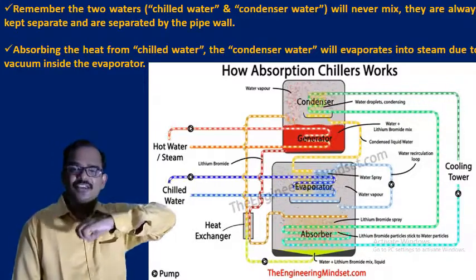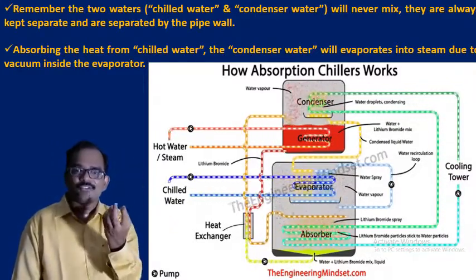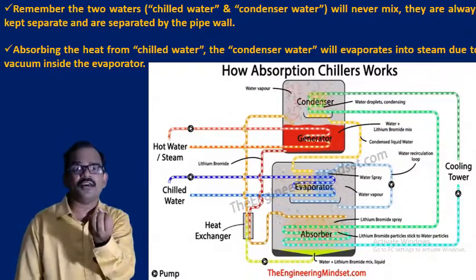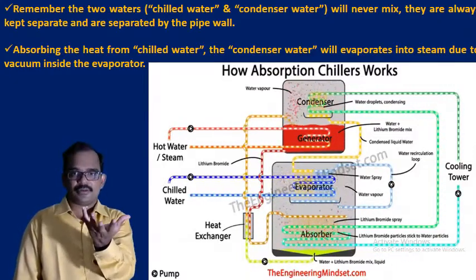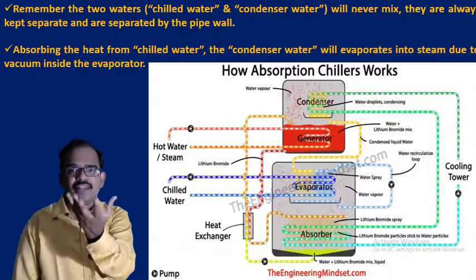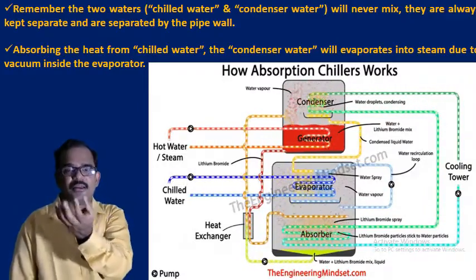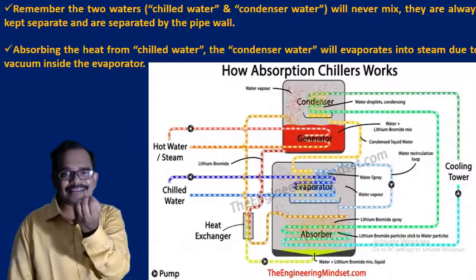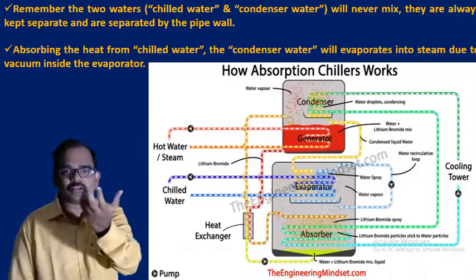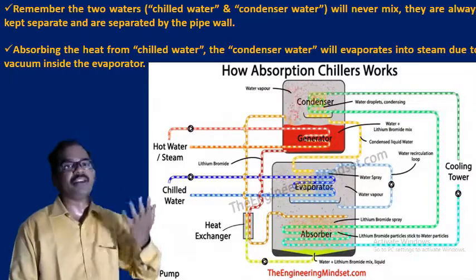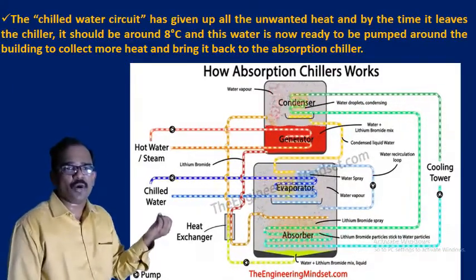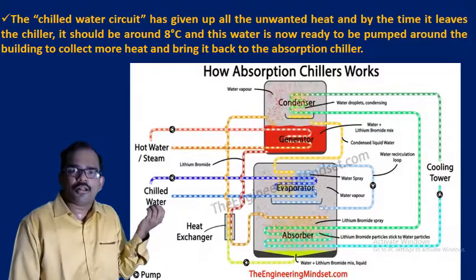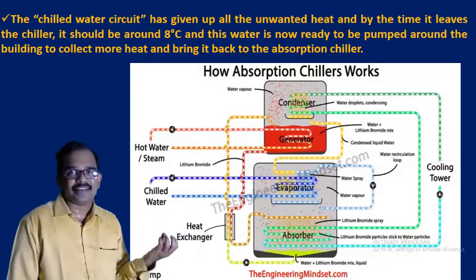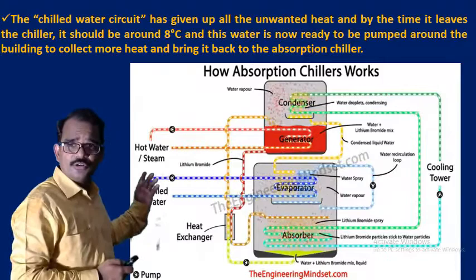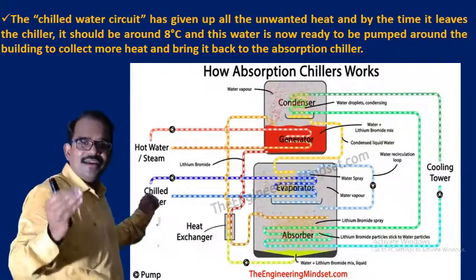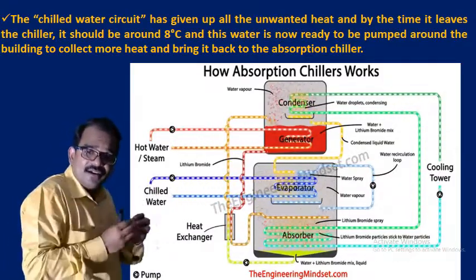So by increasing its temperature from 4 degrees centigrade, the condensed water will now become steam or water vapor, right? And after losing 4 degrees centigrade, this chilled water will now become 8 degrees centigrade, and that chilled water at 8 degrees centigrade will leave the evaporator. So the chilled water circuit has given up all the unwanted heat by the time it leaves the chiller.